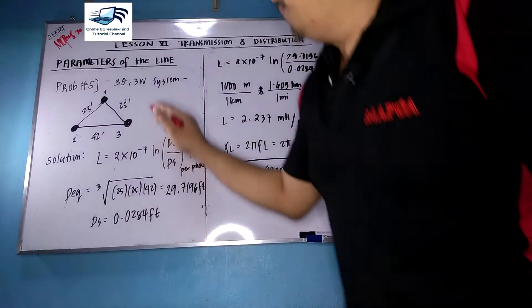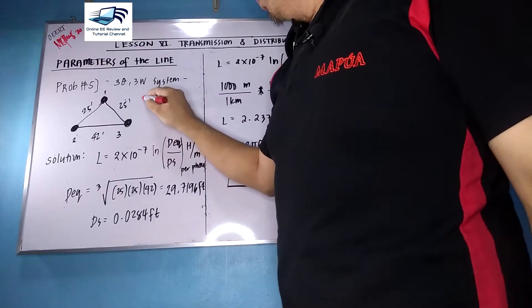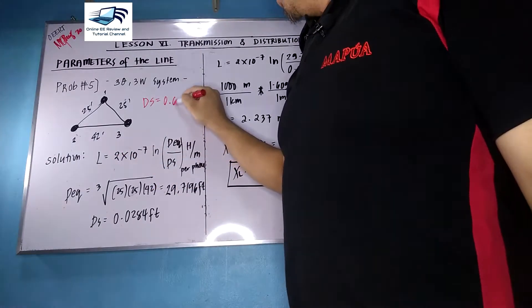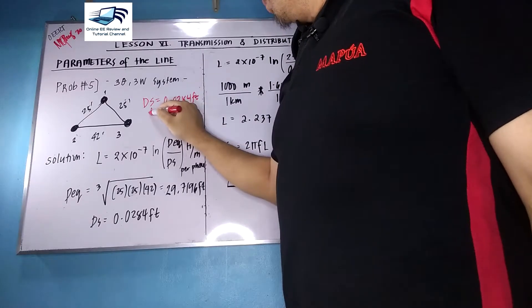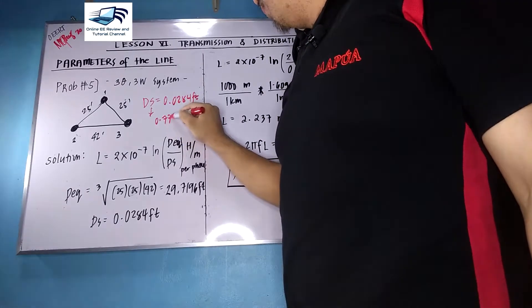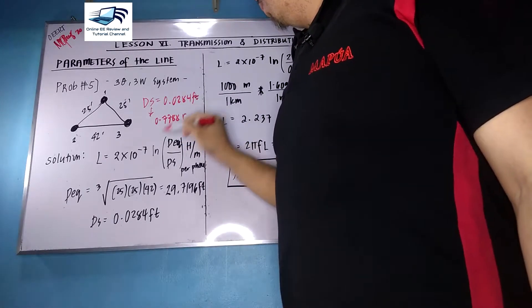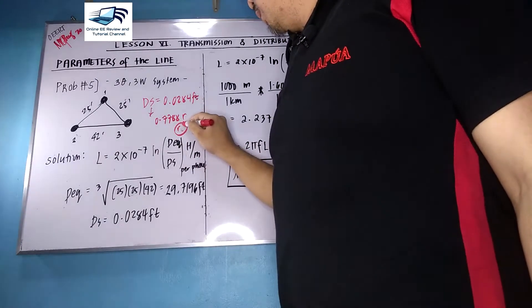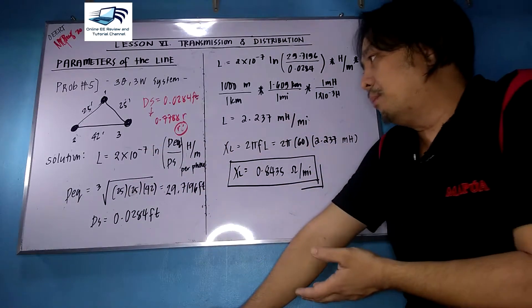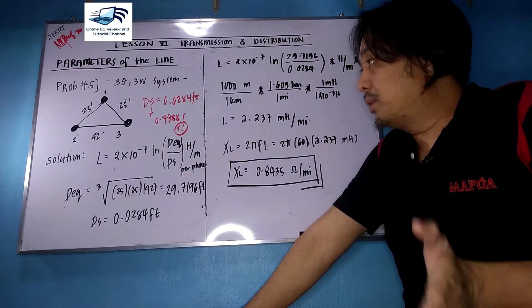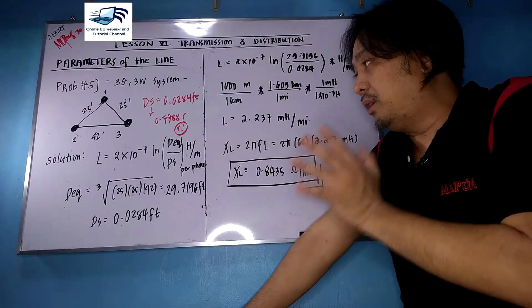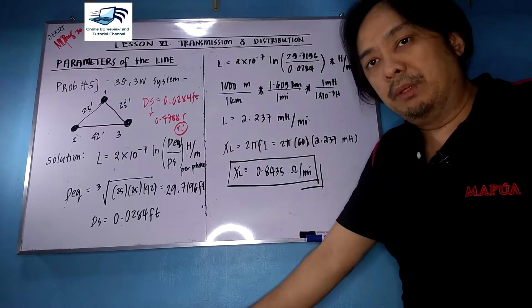We have a three-phase three-wire system. The given DS is 0.0284 feet — please note that DS is already 0.7788 times r, which is the equivalent radius r-prime, also known as the self-geometric mean radius or GMR or self-distance. You do not need to get the radius and multiply by 0.7788 since DS is already given directly.